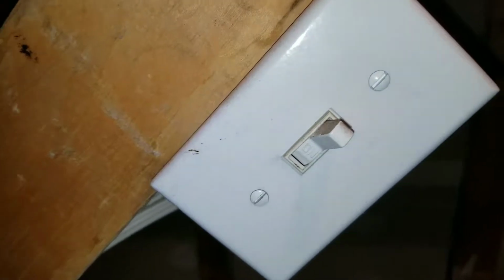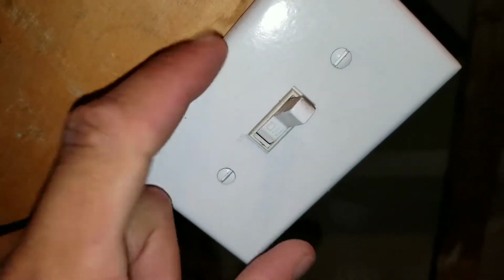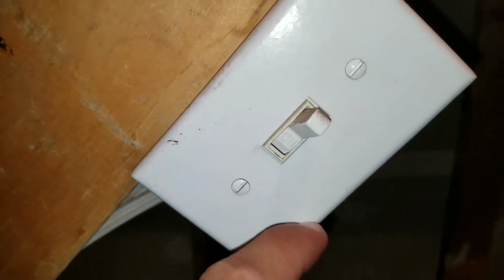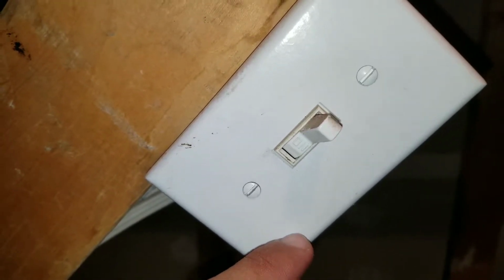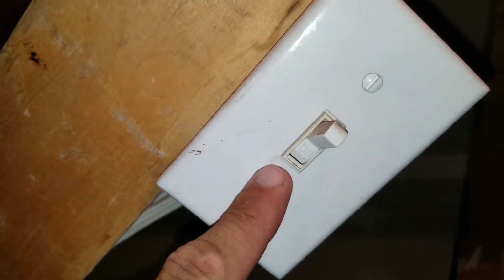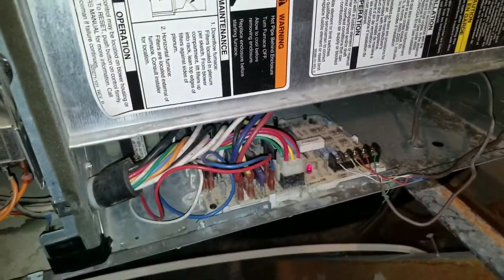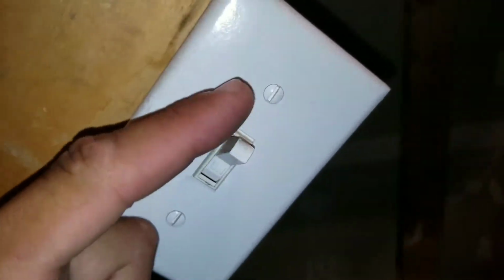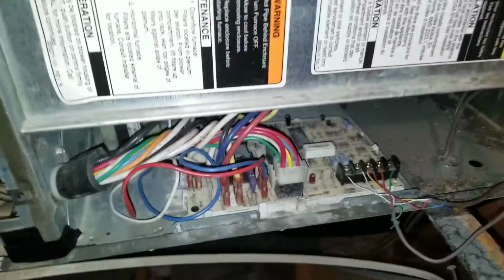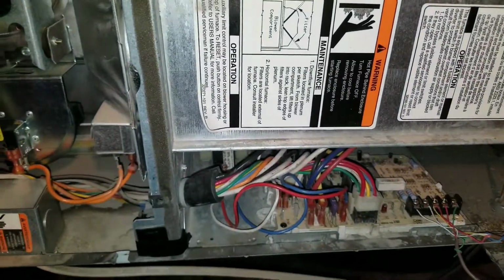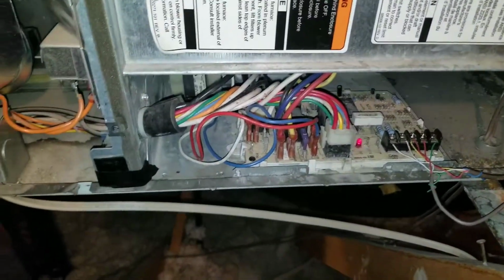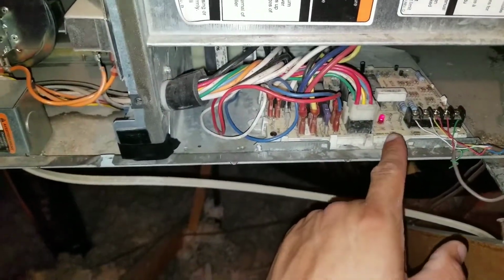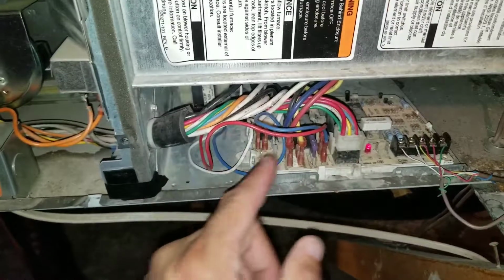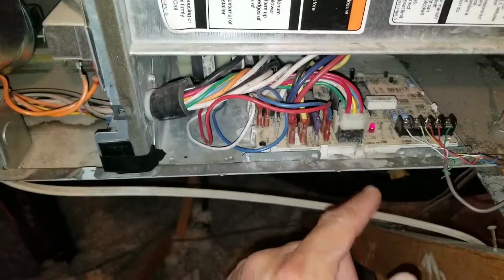Here we have a switch on the wall. It may not be a switch, it may be an actual plug-in and an outlet. This is going to be your power coming directly from the circuit breaker. So here it's in the on position. You can see my LED light is on. Once I turn the switch off, this will remove any and all power to my furnace. We're going to turn our power back on. This will energize our furnace board. The LED light is on, and that indicates to me that I have 24 volts coming from my transformer to the board.